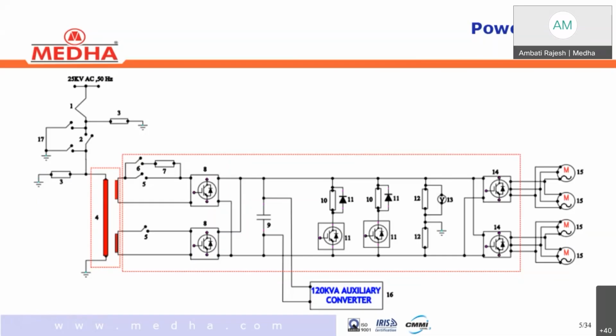Siemens make or ABB make traction transformers, oil cooled, of 1250 kVA rating, provided with 1 primary winding and 2 secondary windings. When the input OHE voltage is 25 kV, each secondary winding produces 950 volts single phase 50 hertz supply. There is no connection between these 2 windings. The single phase AC output from the traction transformer is directly given to the LTC, line and traction converter.